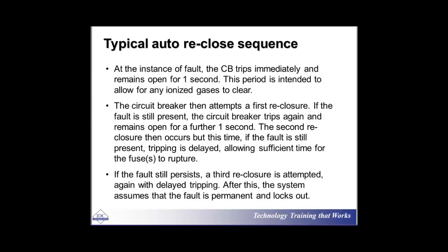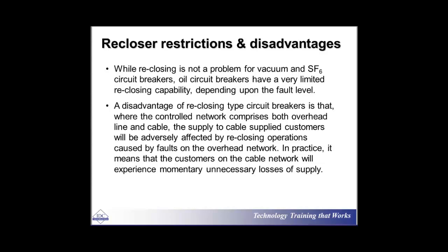That timing of one second or three seconds is in your hands — it is your task to define for the recloser what the delay should be. It all goes back to the I²T of the system, the thermal capacity of the system — how much heat the line conductor or cables can tolerate at the fault current within that time period. While reclosing is not a problem for vacuum and SF6 circuit breakers, oil circuit breakers have a very limited reclosing capability depending upon the fault level — and that goes back to the I²T. This limitation was partly addressed by the advent of SF6 and vacuum circuit breakers.